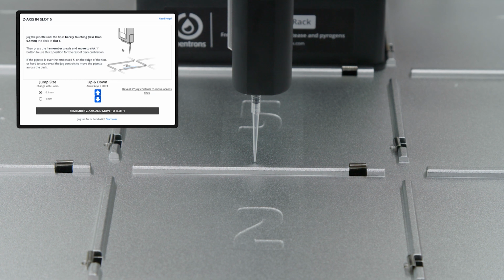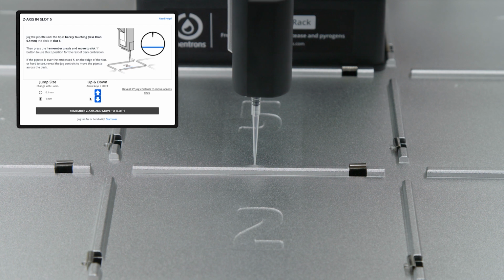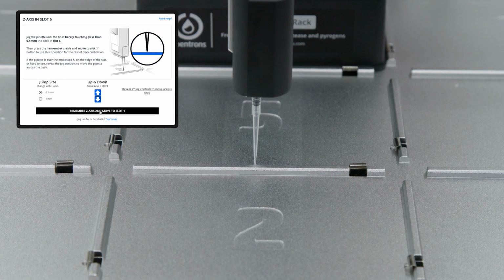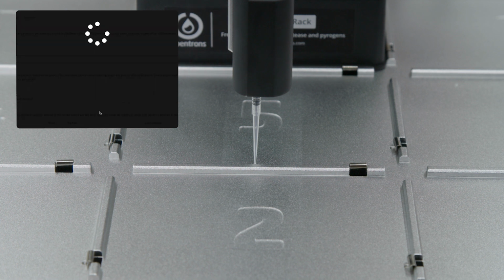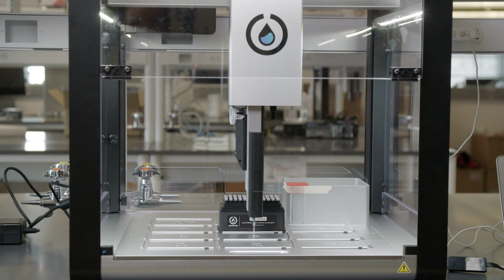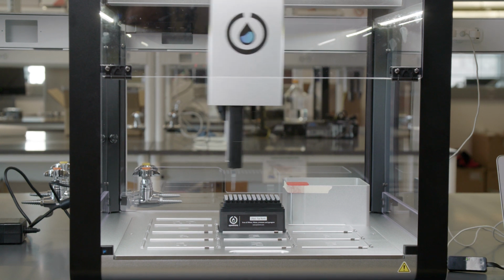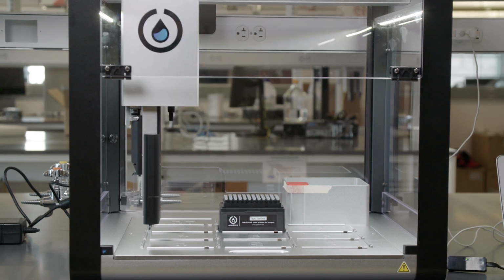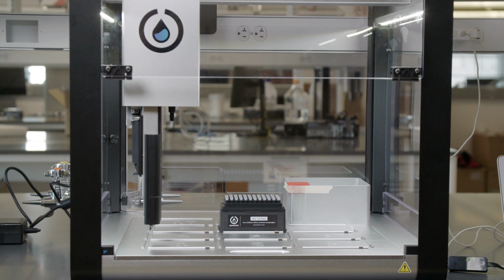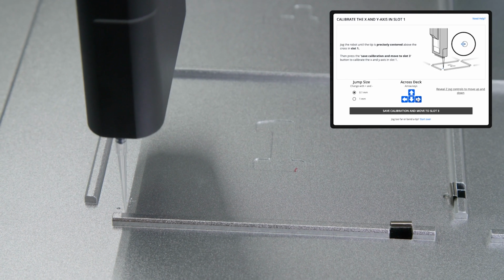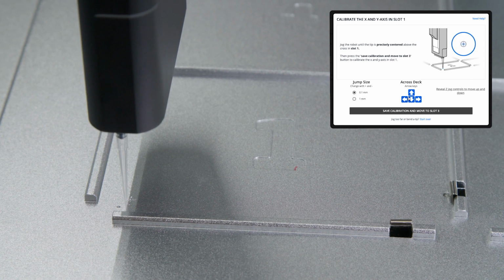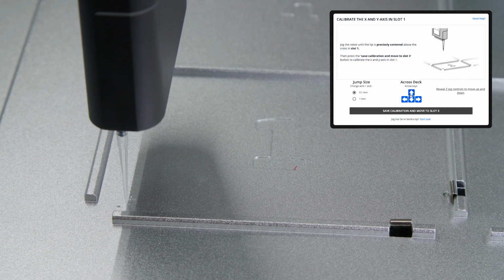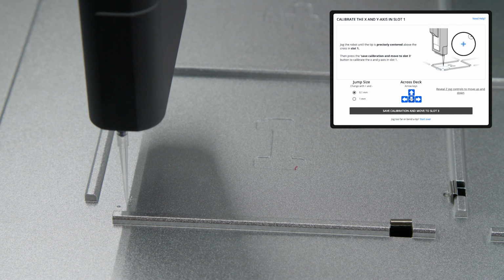I will now jog the pipette so that the bottom of the tip is barely touching the deck. So the pipette is less than 0.1 millimeters from the deck. I will remember this position, and the pipette will then move to the cross in slot 1. The pipette is now in slot 1, and I need to position the pipette so that it is centered in the cross. To do this, I will use the app and select the arrow keys.